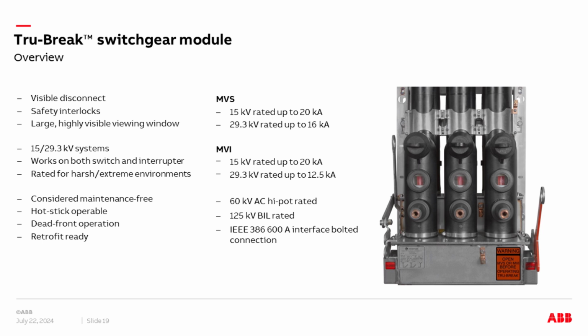And a quick question here from a utility. I'll just throw it in here real quick, Abe. Utility wants to know, can these vacuum interrupters and switches be fused? So these are not fused. The devices I showed, the interrupter is programmable to replicate a fuse. So you can pick from standard industry fuse curves. I'll show one in a minute. You also have the capability to manipulate the shape of the curve and some other characteristics around curve delay. So it acts as a fuse, but it's not a fuse. So it's resettable without having to replace any parts.